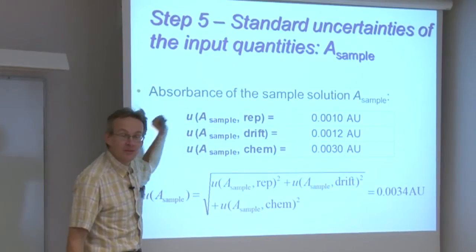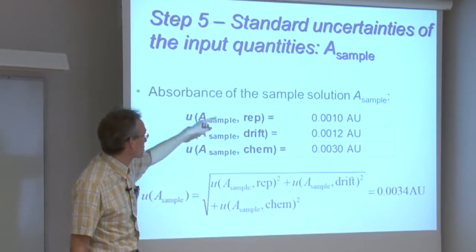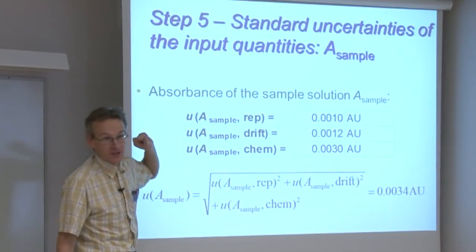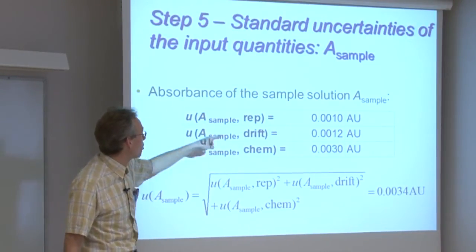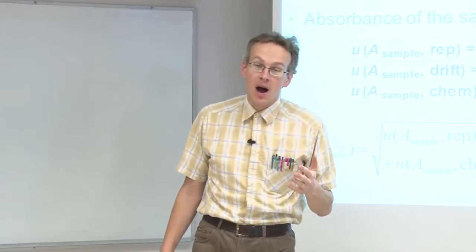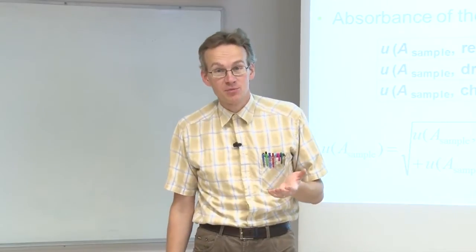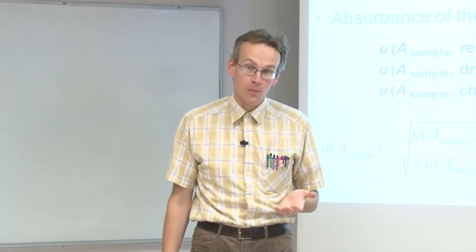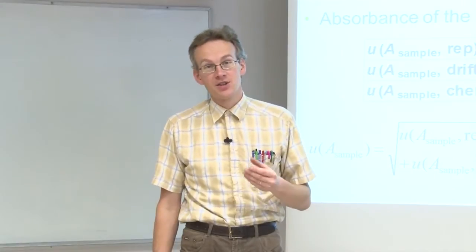Repeatability of the photometric reading, possible drift of the photometric properties, and also possible chemical interferences which can come either by increased absorbance because some other compounds also absorb at the used wavelength, or by decreased absorbance because something causes the dye either not to form or to partially decompose.